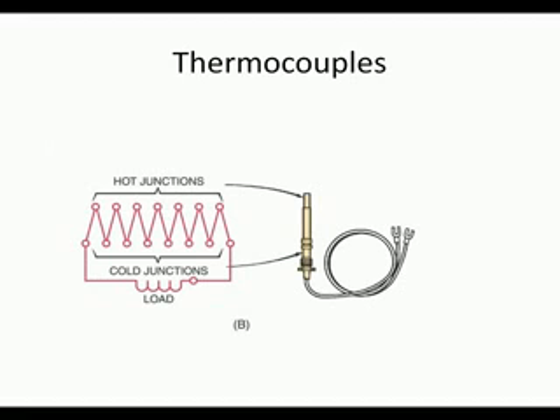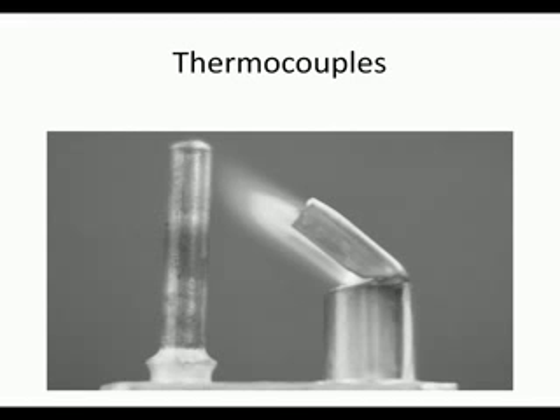A thermocouple is constructed of two dissimilar metals. In other words, it might be two different types of brass and copper, or two dissimilar metals. When heat is applied to the joint, the voltage is created. A thermocouple will produce up to 30 millivolts. Thermopiles, sometimes known as power piles, will create either 250 millivolts or 750 millivolts.